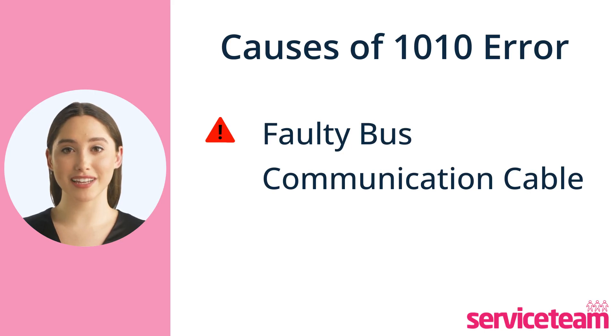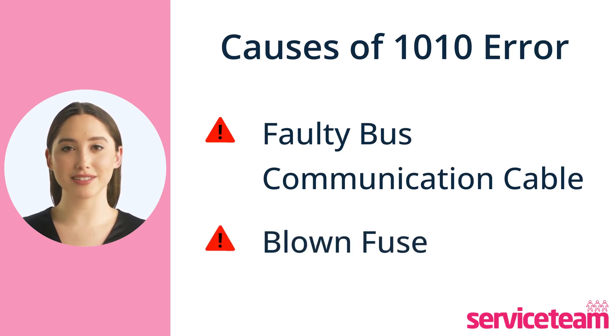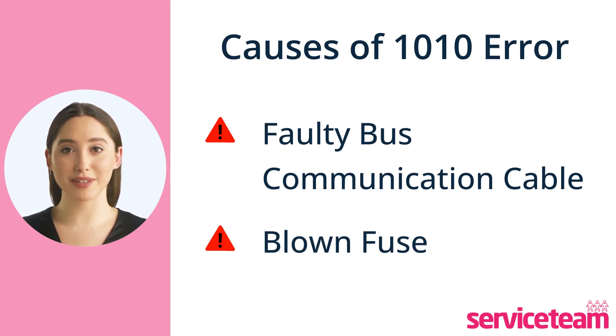Secondly, if the fuse is blown in the damaged cable, it can also cause this error code because it stops signals from traveling properly through the bus communication cable.